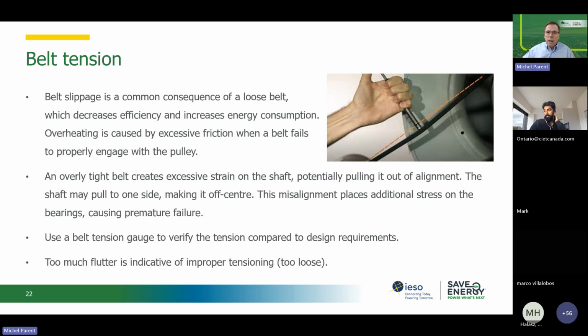All of what we're talking about right now will result in energy waste. Improper belt tensioning, misalignment will result in energy waste. Running motors too hot will reduce their efficiency, energy waste. So basically, almost all of what we're discussing today will result in energy waste. And actually, in the last section, we do quantify that, based on different case studies, of how much you can gain in energy efficiency just by proper diagnostics and preventive maintenance to prevent failures of your system.